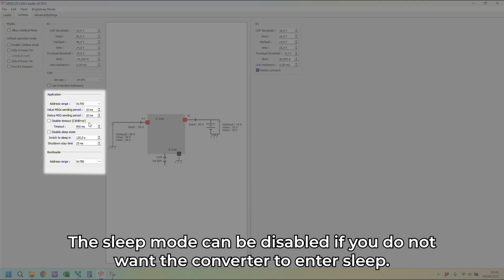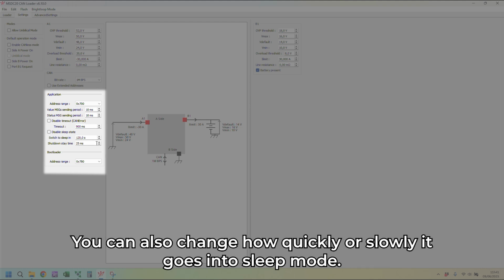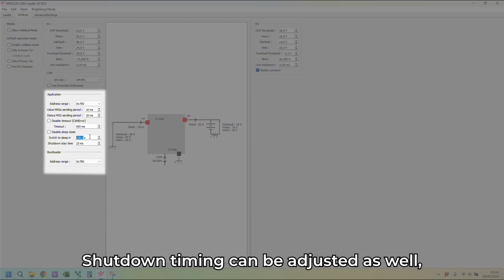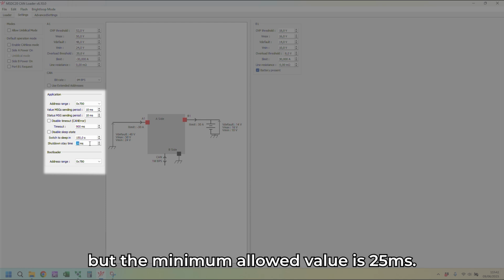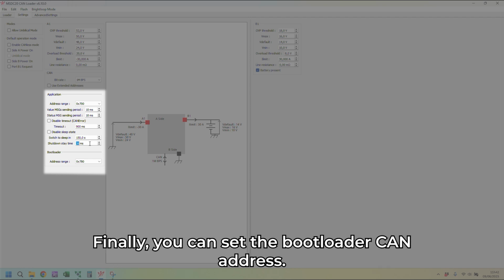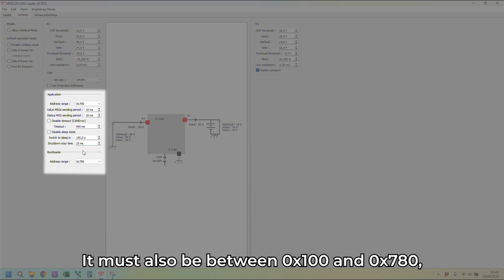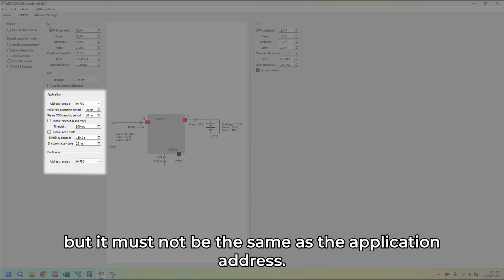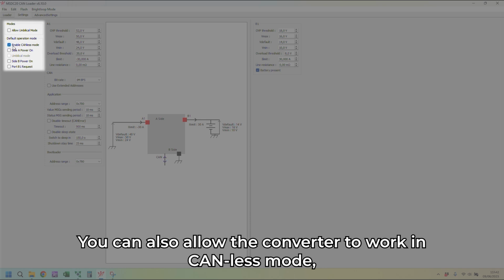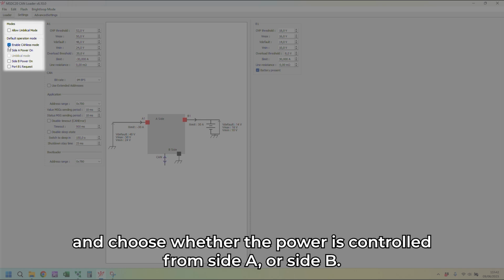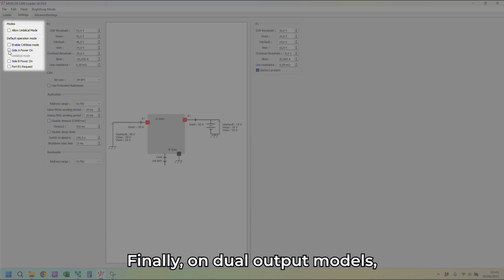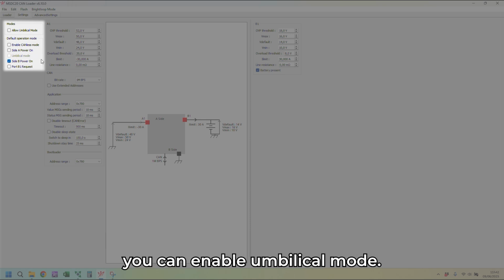The sleep mode can be disabled if you do not want the converter to enter sleep. You can also change how quickly or slowly it goes into sleep mode. Shutdown timing can be adjusted as well, but the minimum allowed value is 25 milliseconds. Finally, you can set the bootloader CAN address. It must also be between 0x100 and 0x780, but it must not be the same as the application address. You can also allow the converter to work in CAN-less mode and choose whether the power is controlled from side A or side B. Finally, on dual output models, you can enable umbilical mode.